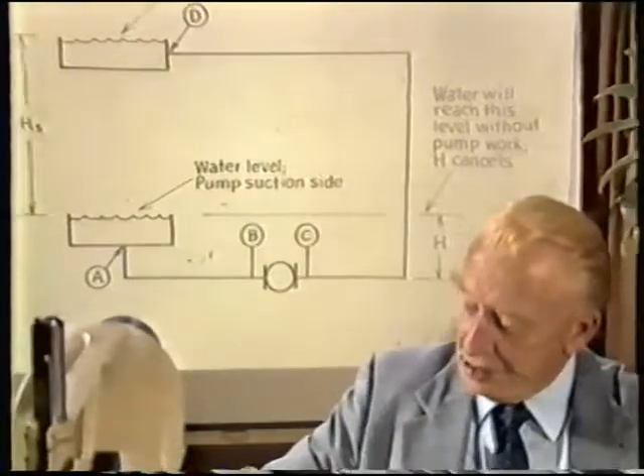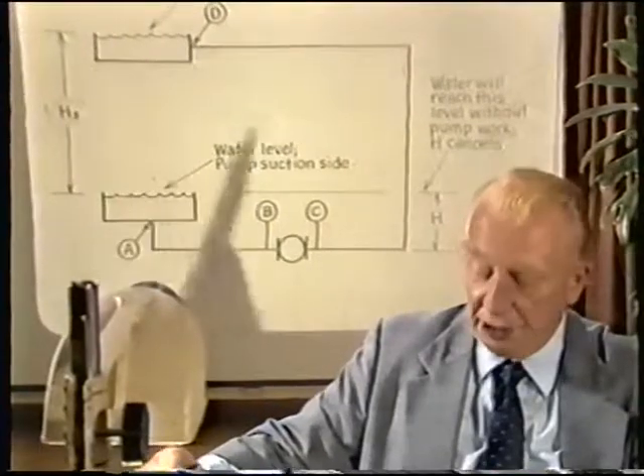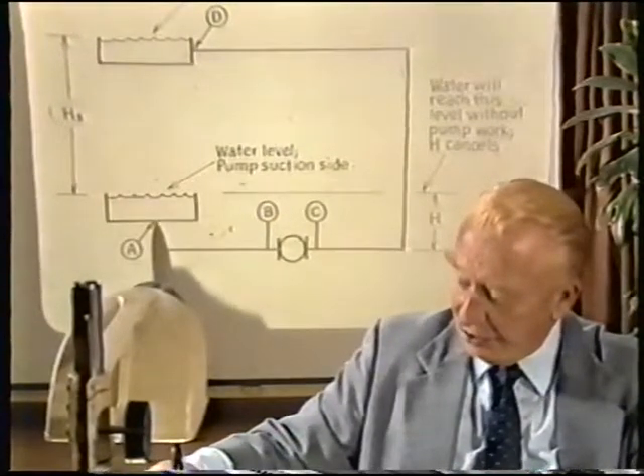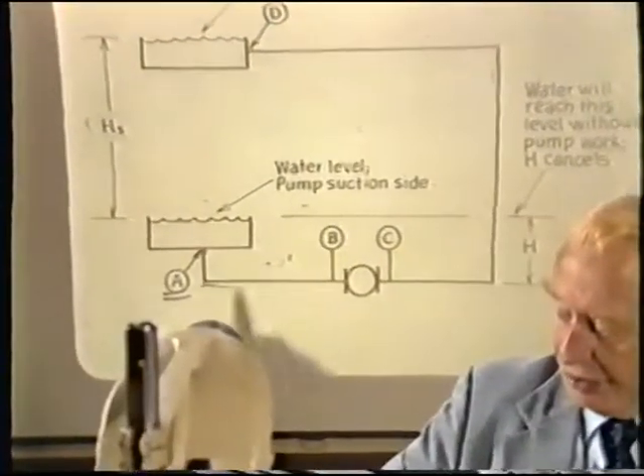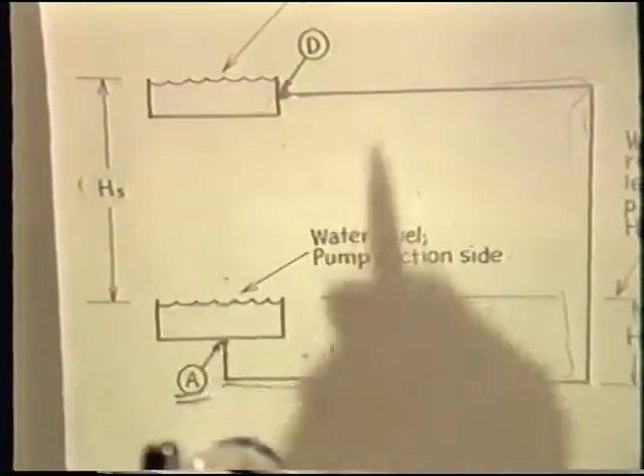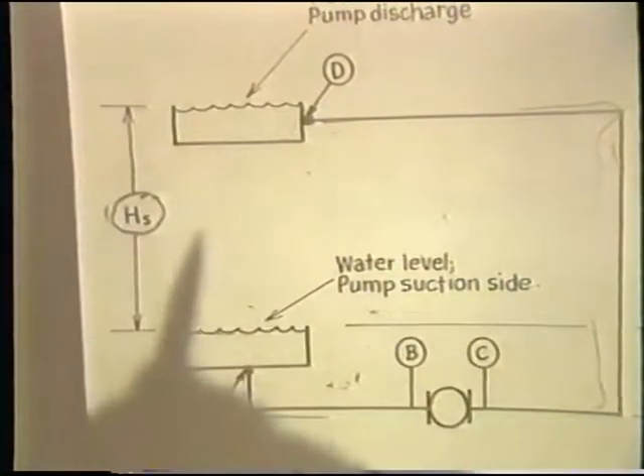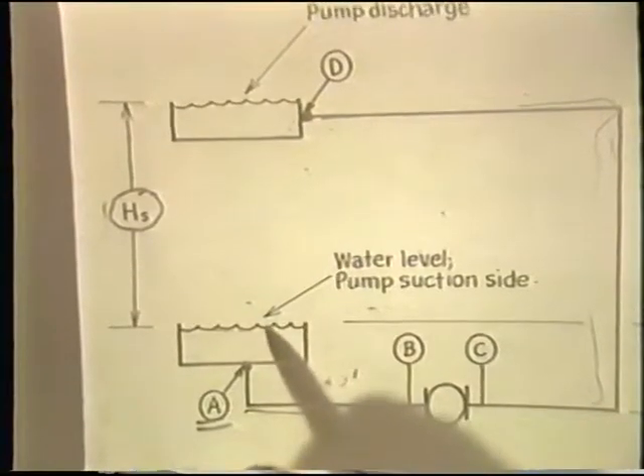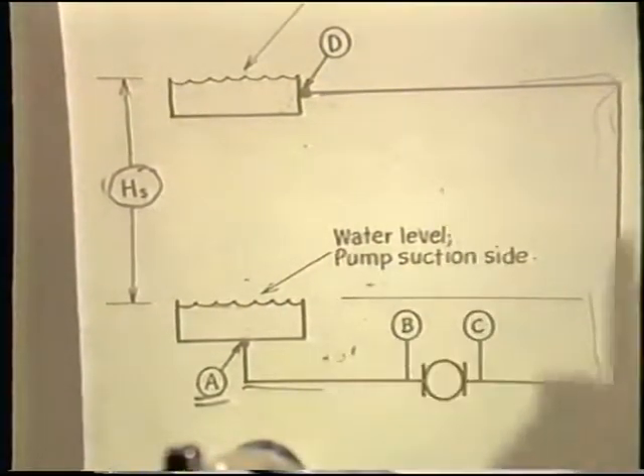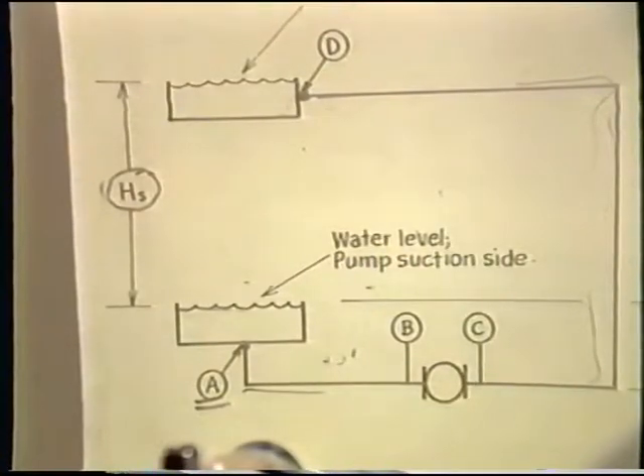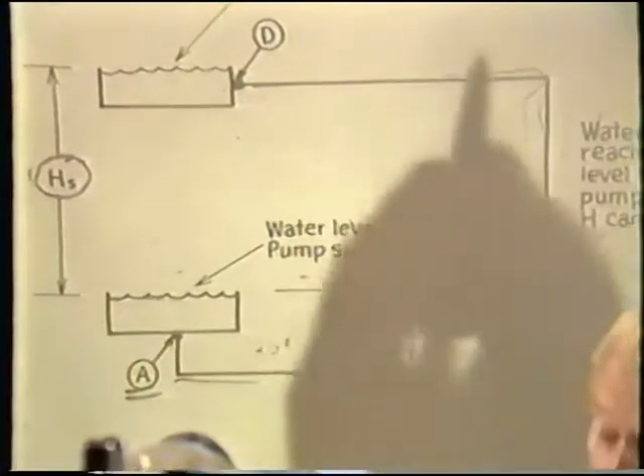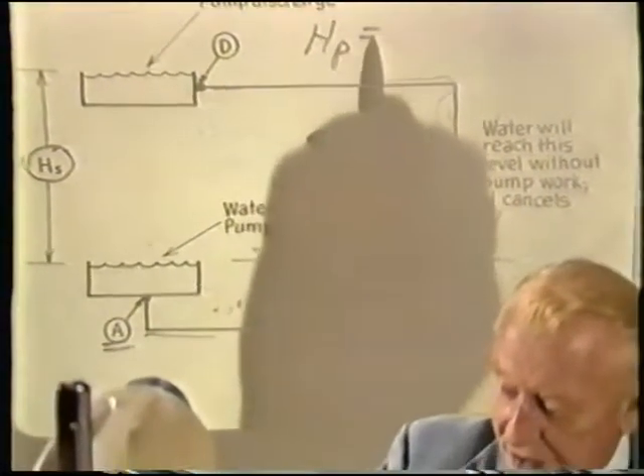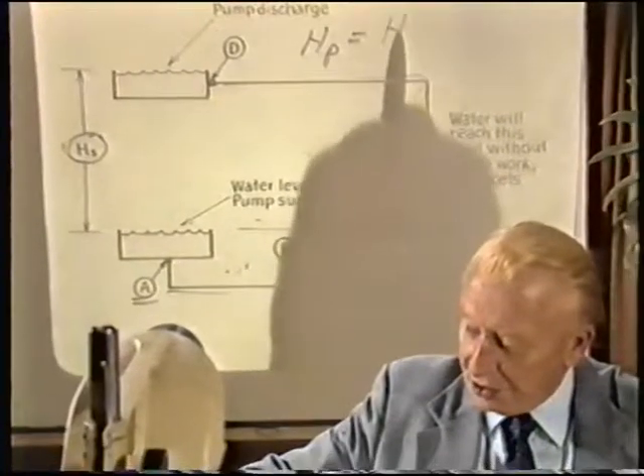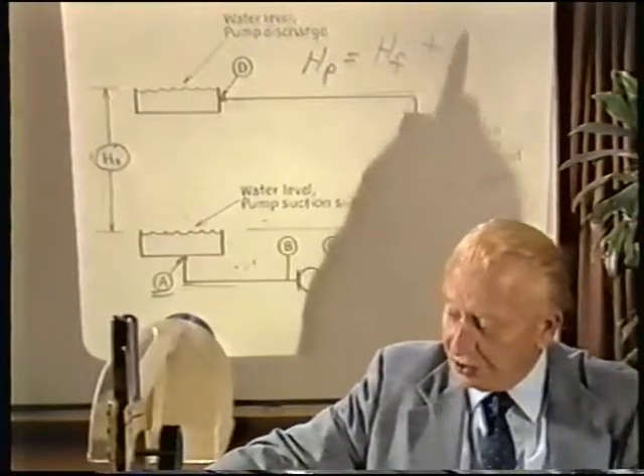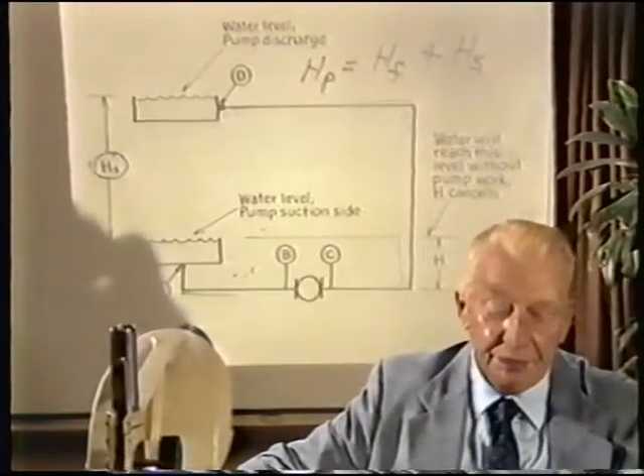Now, for the open type of piping system, where we are pumping from one water level to another, we must take into account not only the friction loss as from A through the piping system and to D, but we must include the static height difference between the low water level and the high water level. So for the conventional open type of system, then, the pump head is equal to the friction loss in the piping system itself plus the open statics of the system.